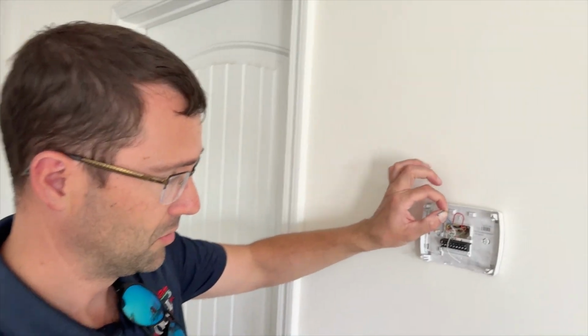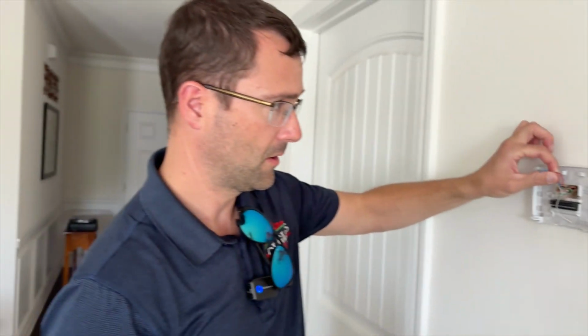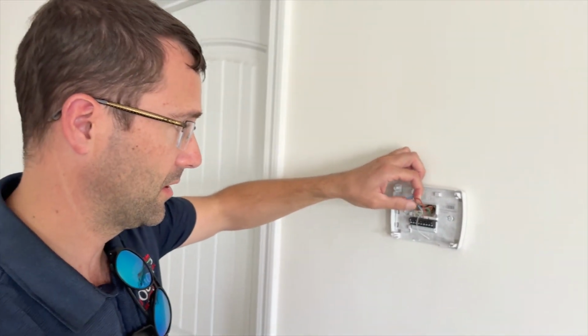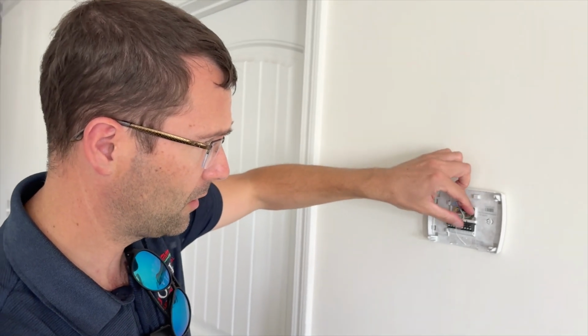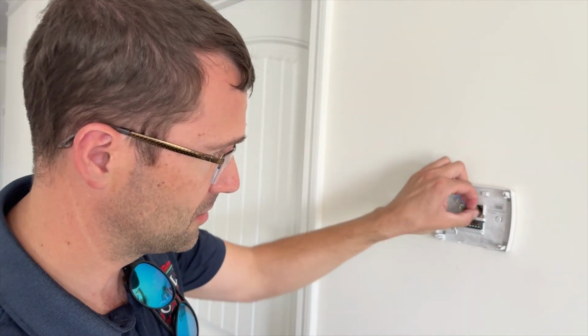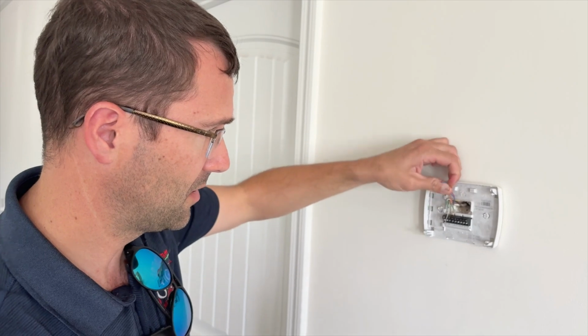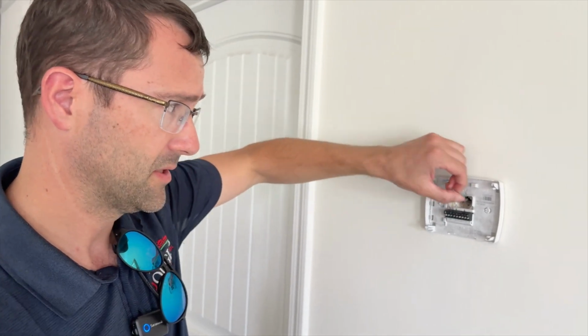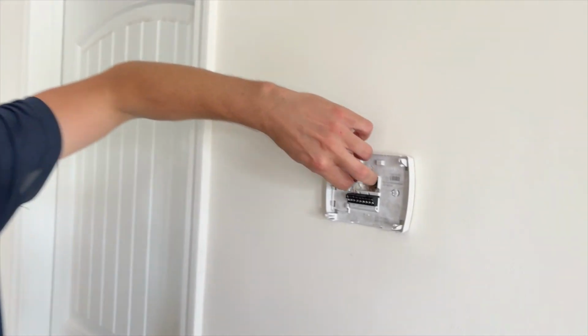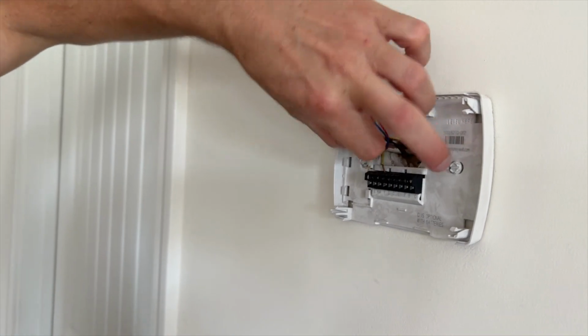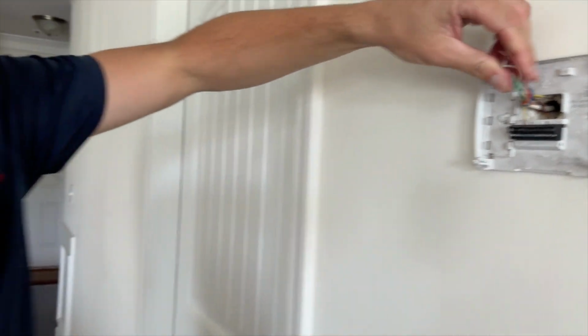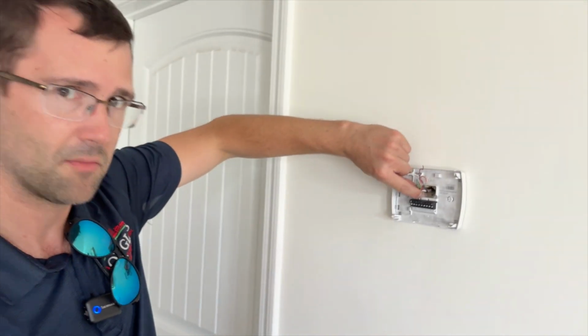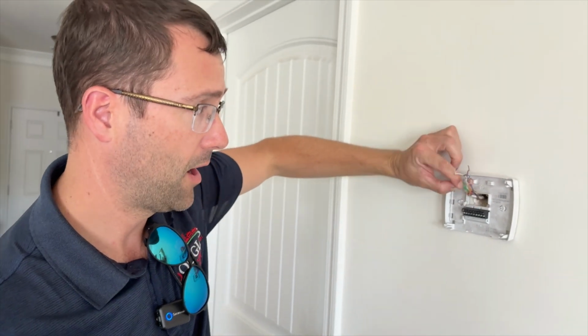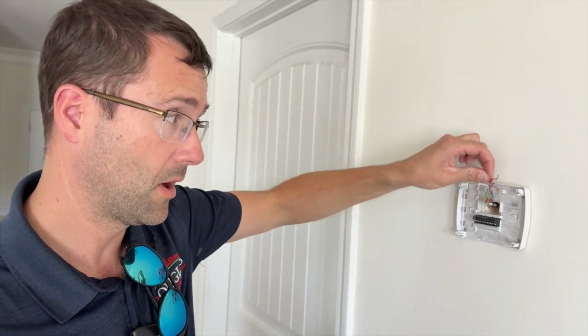So blue was my common wire, red was my power wire. Next thing I got is an orange wire, that's my reversing valve. Got a green wire here, that's my fan. I'm going to go ahead and pull the white wire out, that's my auxiliary heat or emergency heat, depending on how you want to say it. And then I got Y here, which is my yellow wire, which is my compressor.